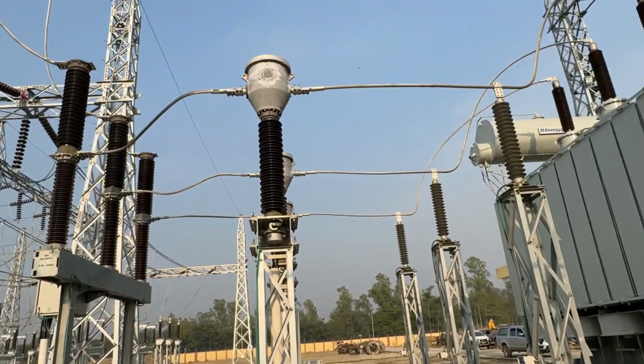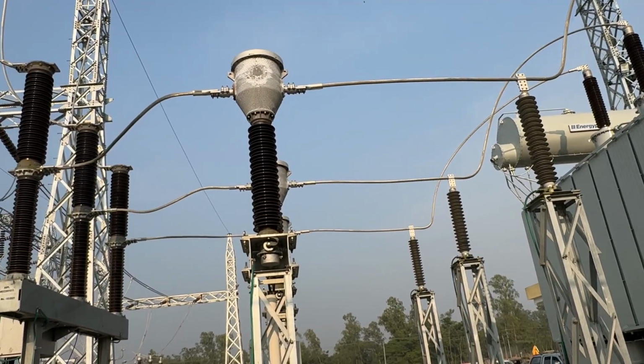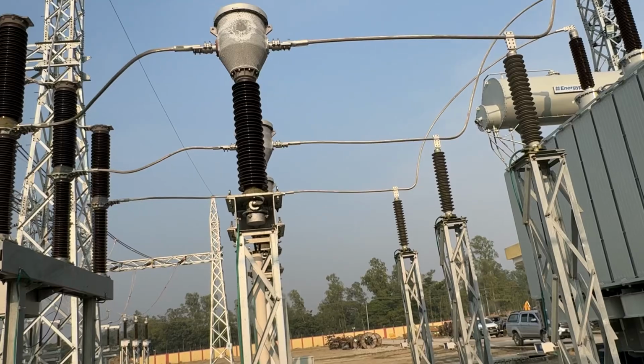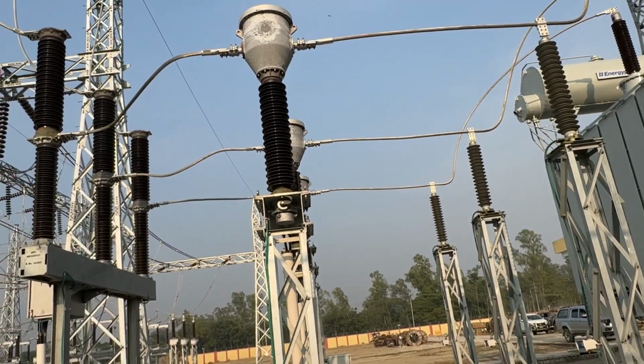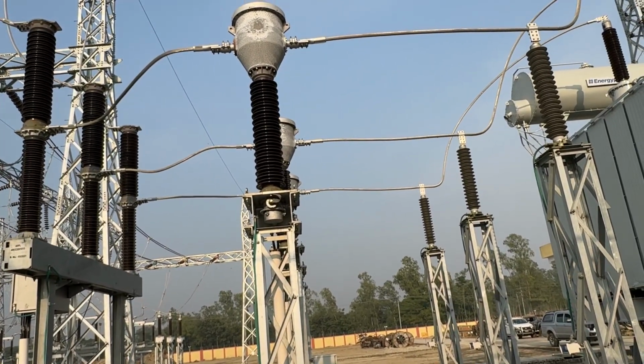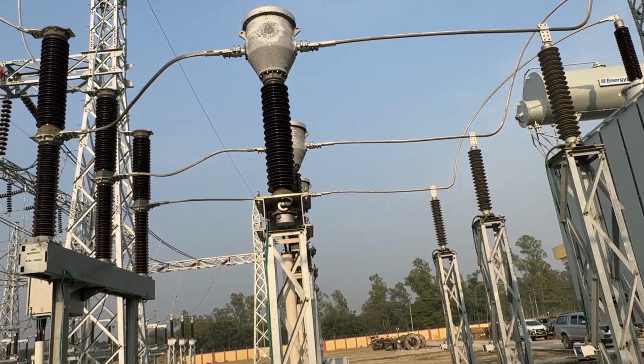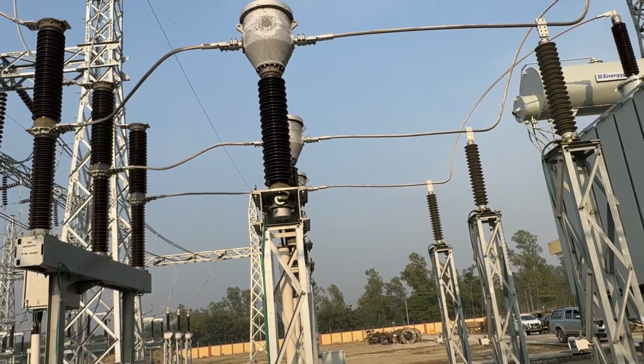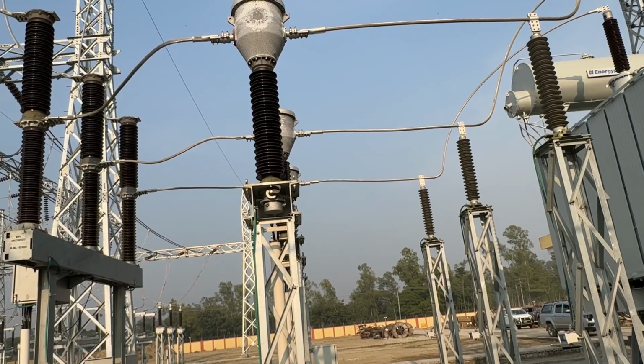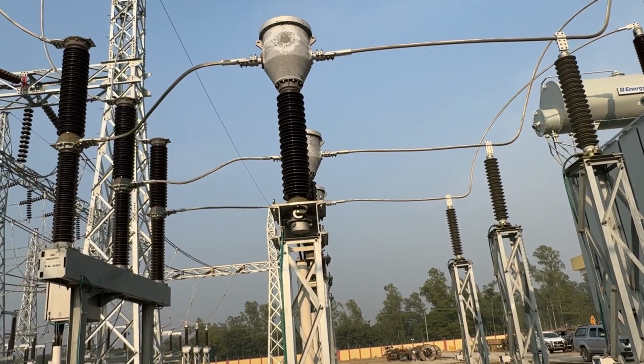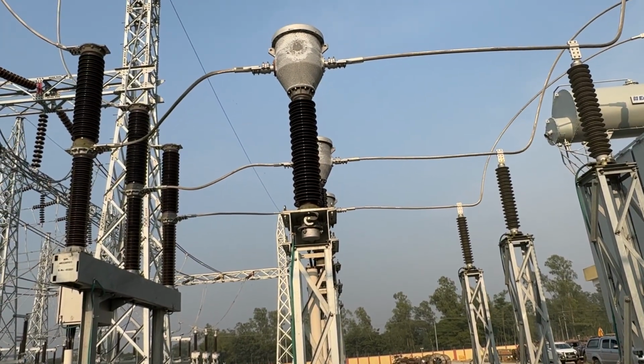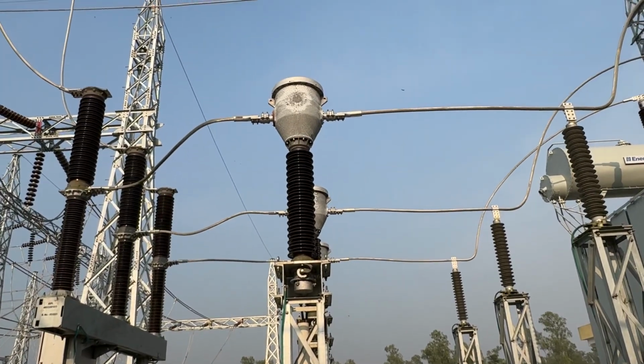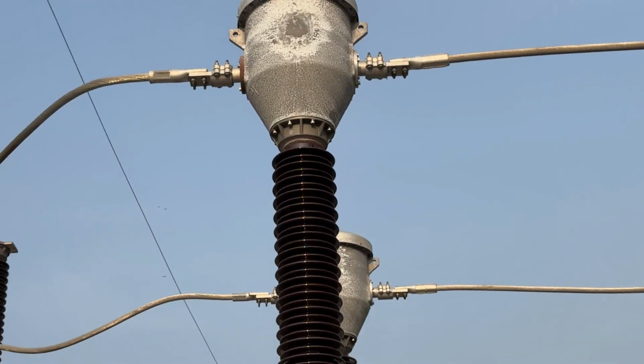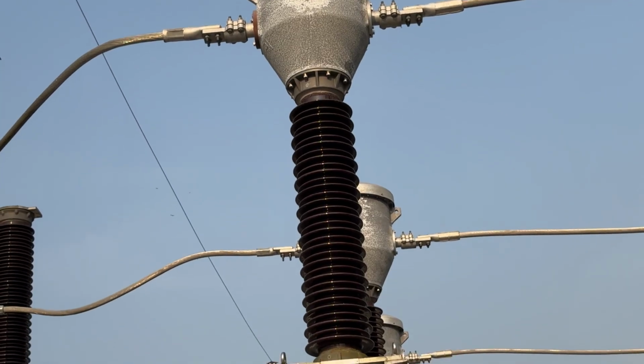There is a current transformer. It is used to measure the current. In a nameplate, it is shown that the primary side current, maximum current, is up to 500 ampere, but it is not possible to measure 500 ampere directly. So this CT converts 500 ampere to either 1 ampere or 5 ampere.